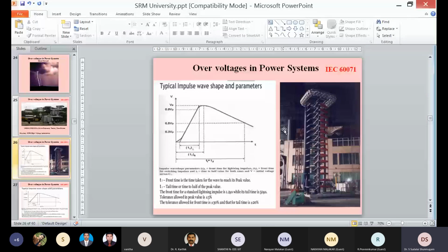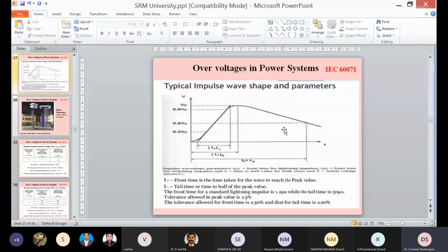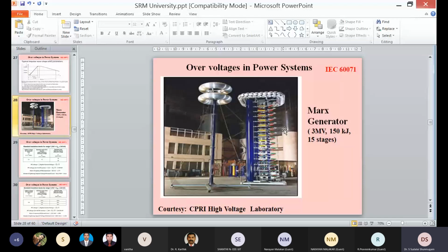In the laboratory, you generally use a Marx circuit or Marx generator to generate lightning impulse voltage. And of course, there are different waveforms, and this is the standard waveform. Different equipment will be tested with different waveforms and different per unit values. I just elaborated on that. In Bangalore, we can test up to 3 million volt. The Marx generator we have is capable of generating 3 million volt and supplies an energy of 150 kilojoule. The number of stages is 15 in order to generate lightning impulse voltage.